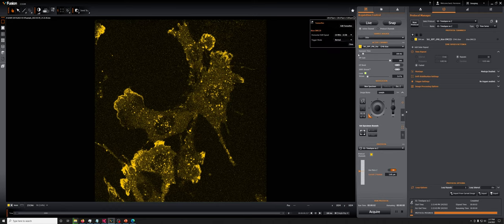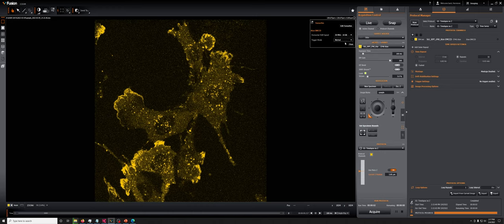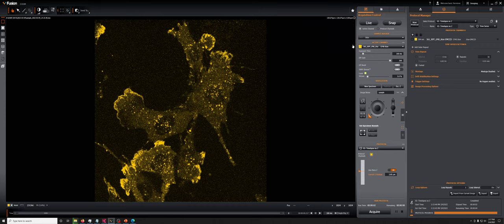So if you want to go fast, the first thing is just to make sure you're at 30 megahertz. At 10 megahertz, you are slower by a factor of 3, which is the difference between 30 and 10. So that is the first thing that you need to make sure of if you want to go fast when you're imaging with this camera.